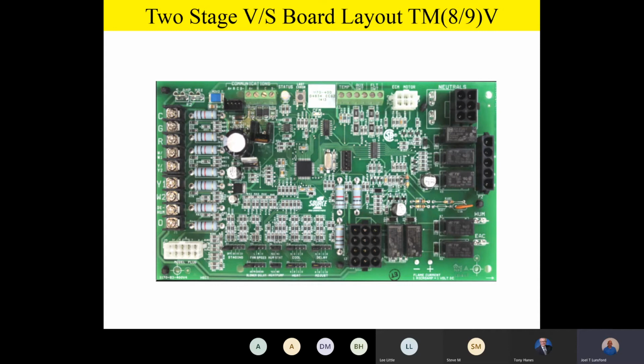You're going to have a control board and some jumper selection for your airflow selections instead of physically moving a wire on the control board or on the motor itself to select speed taps. In addition, on the variable speed board, we're going to change our terminology a little bit. As we talk about cooling airflow and heating airflow on a variable speed product, we start using the terms percentage of airflow. As we talked about high and low airflow before, Y1 and Y2, on this board I'm going to start referencing percentage of airflow when we have a Y1 and percentage of airflow if we have a Y2 second stage cooling call. So be prepared for that. But other than that, this is pretty straightforward.